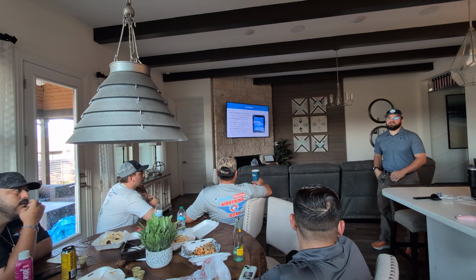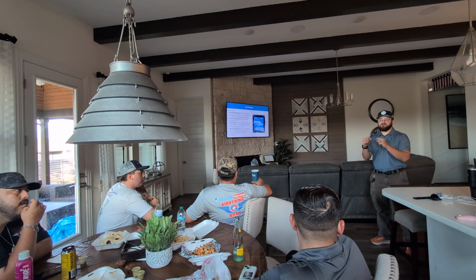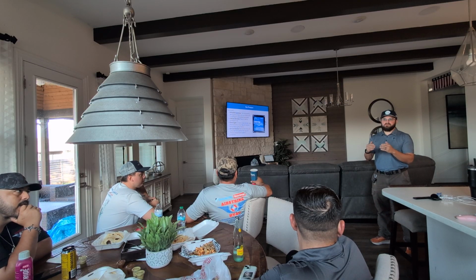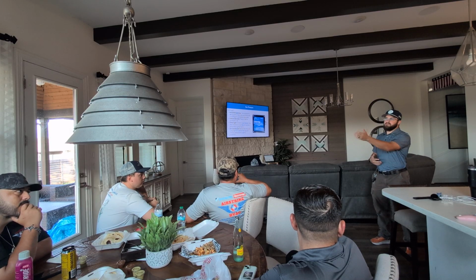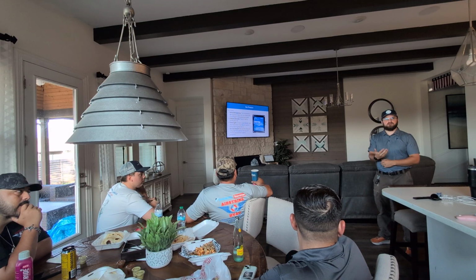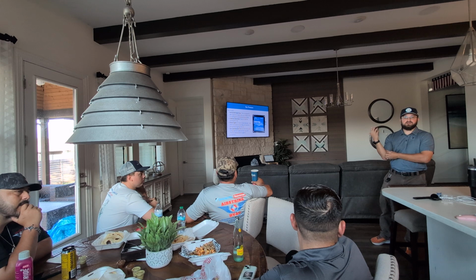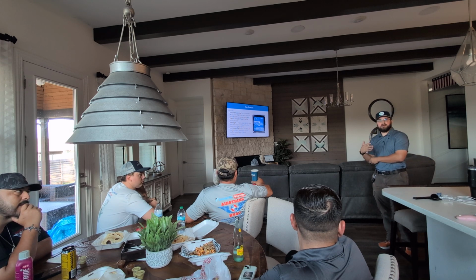Your house experiences several hundred mini surges, they call them transients, so it's not a full surge, but several hundred transients throughout the day. A surge comes through every time the power goes out, a lightning storm hits, new construction happening down the road, all of that's going to cause surges. I guarantee they're having a surge come through, it's just a matter of how severe it is. But unless the red light's on, this thing protected against the surge.